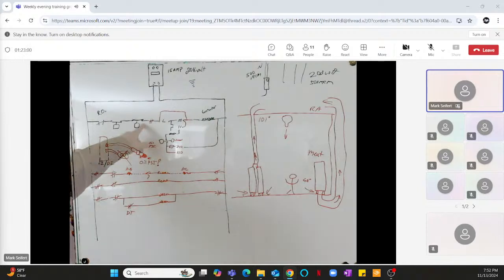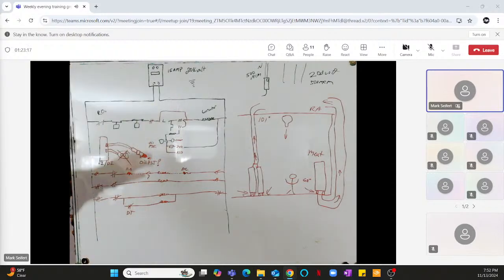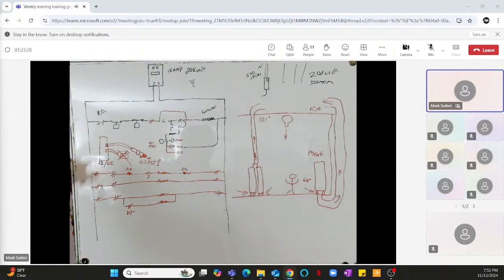You've got to make sure it's not tripping on high pressure. You've got to make sure that it's not short cycling on the low pressure control. You've got to make sure that there's not a loose wire at the contactor. There's a whole bunch of things that you're going to want to look at when the controller is doing it. But just so you know, it's nothing more than just a signal telling it whether you've got oil pressure or not, whether the compressor's running or not.